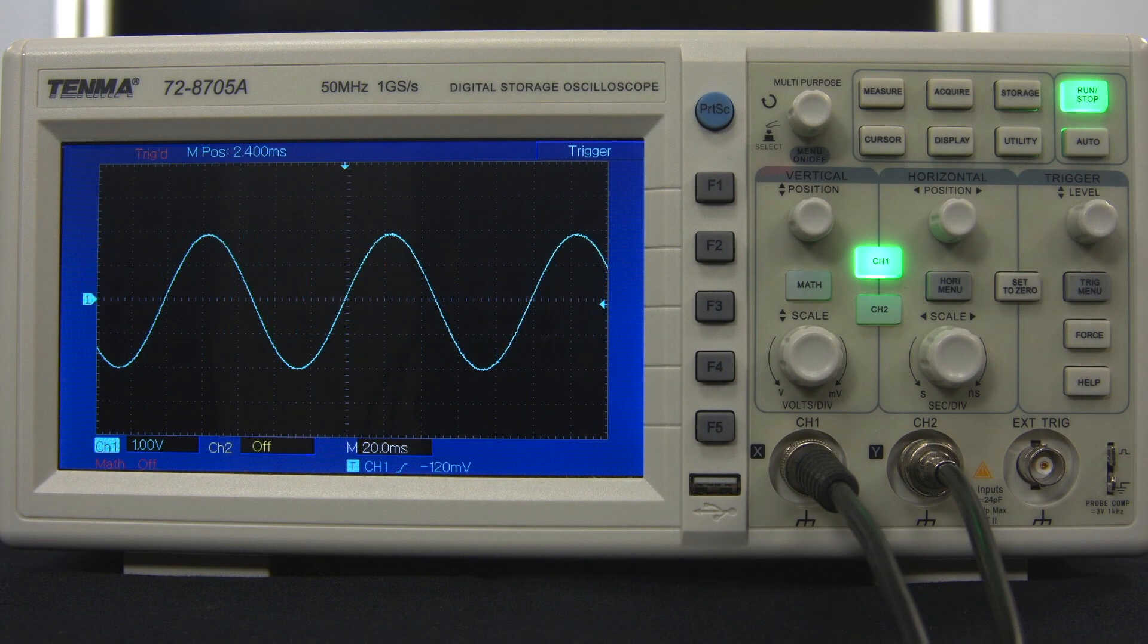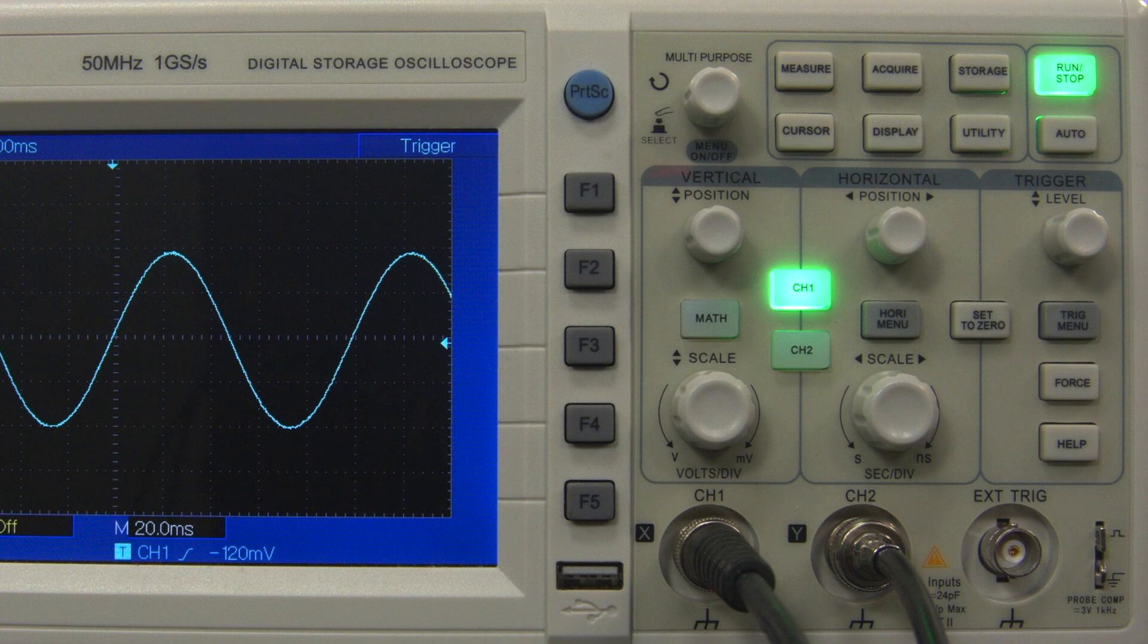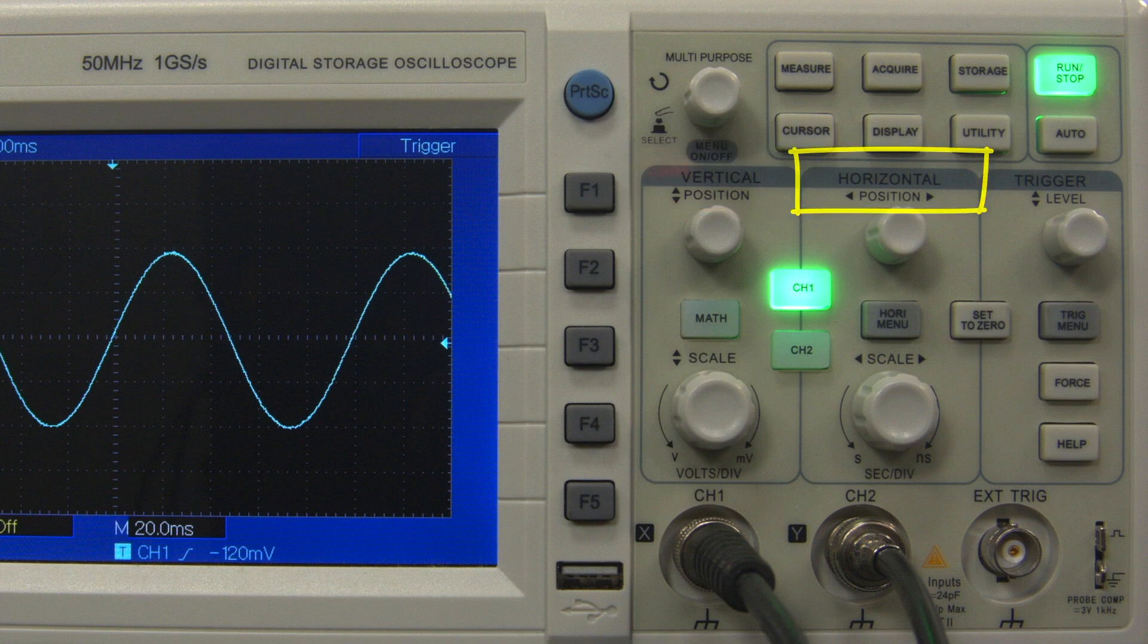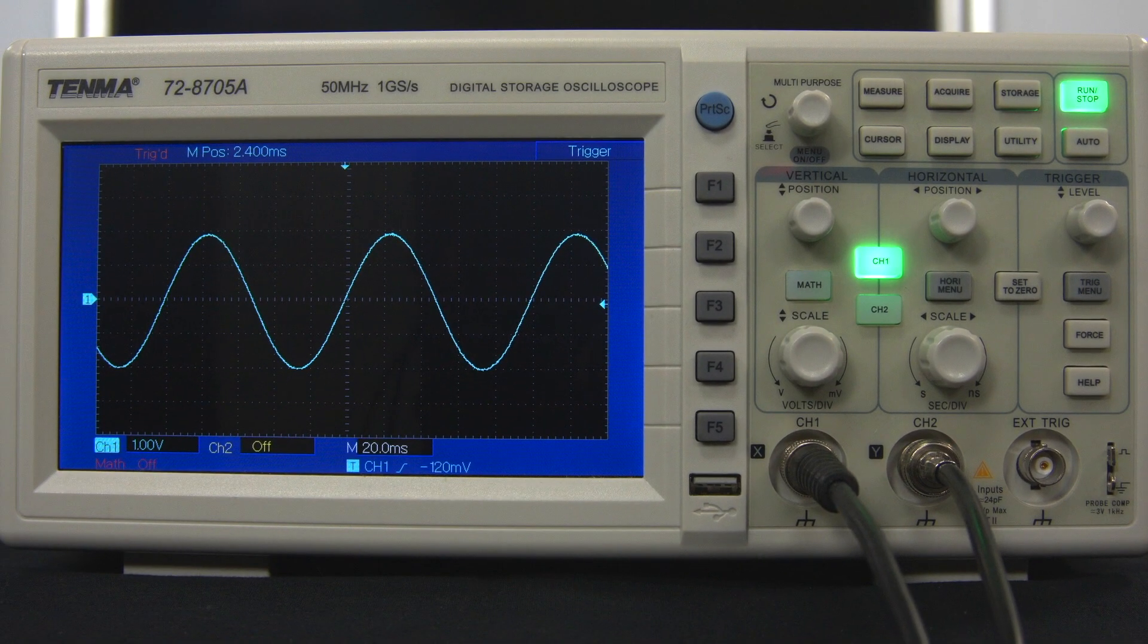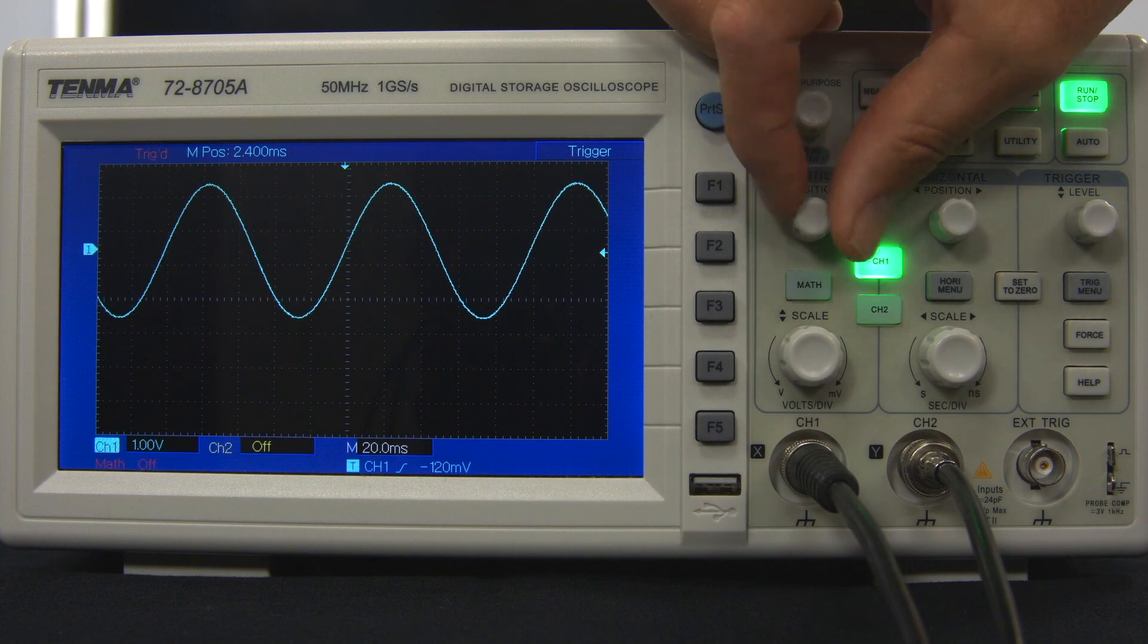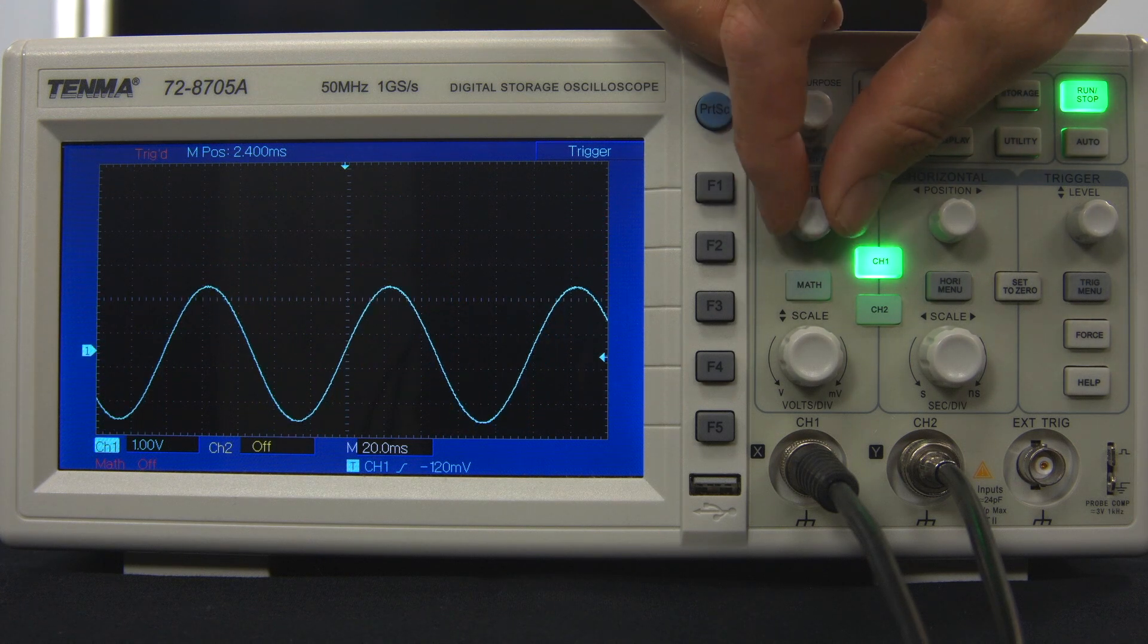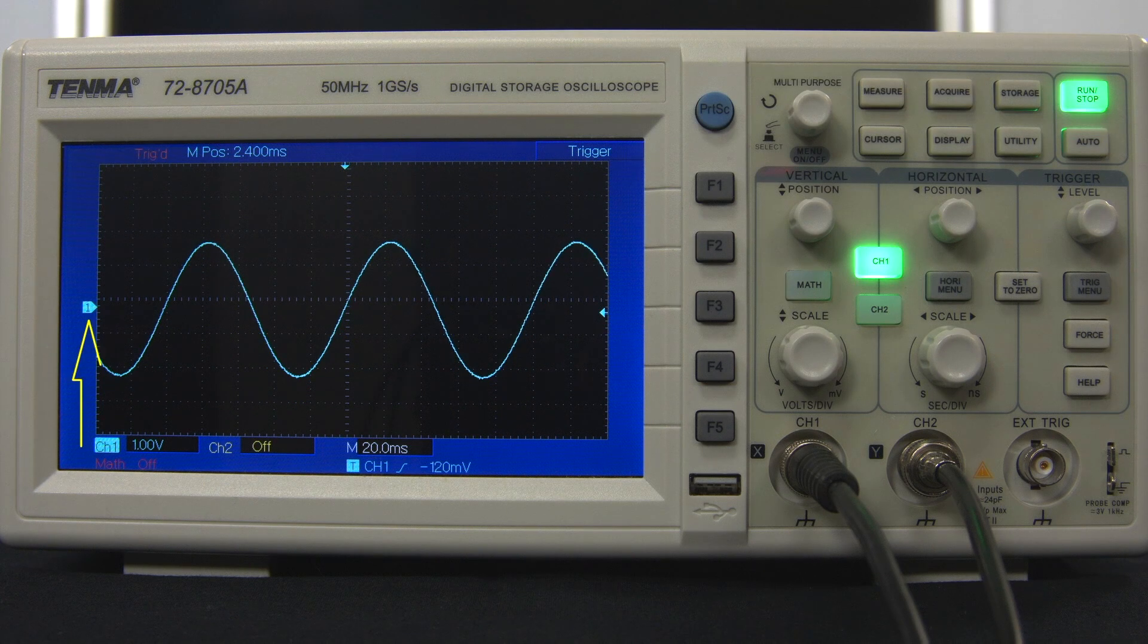Now let's look at the controls on the right hand side of the oscilloscope. The main controls are arranged in three groups labelled at the top: vertical, horizontal and trigger. Starting with the vertical controls, the position knob moves the signal up or down on the screen. The location of the zero voltage is always indicated on the screen by the arrow on the left.